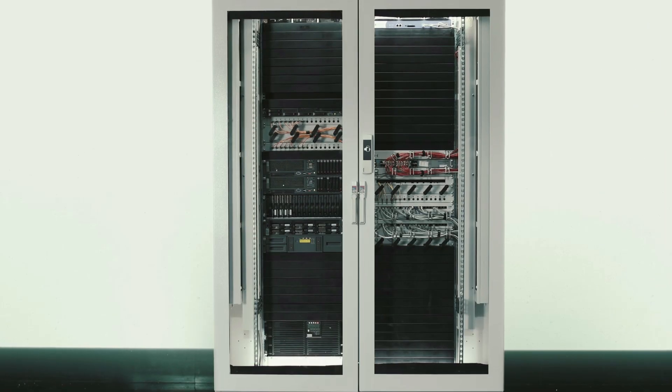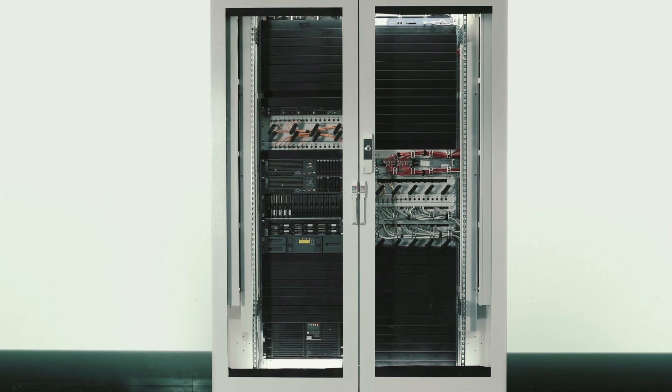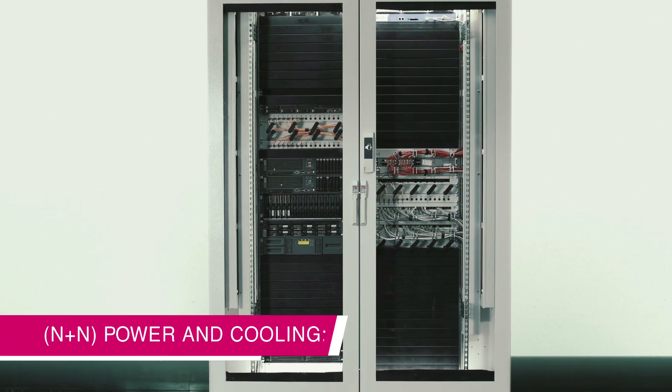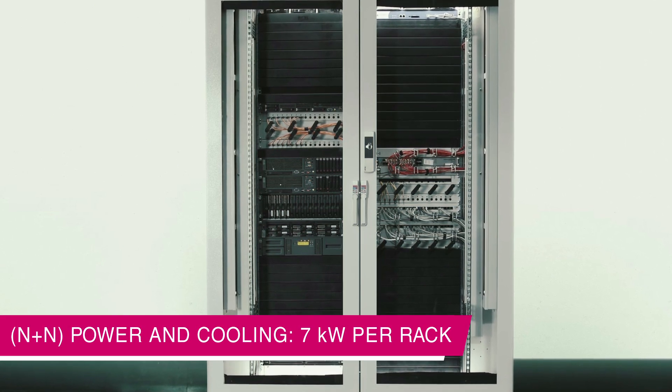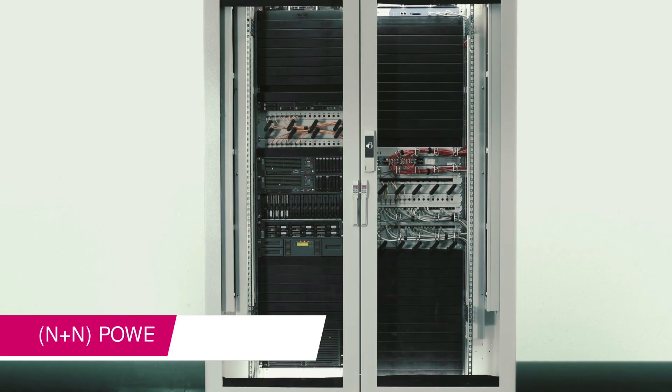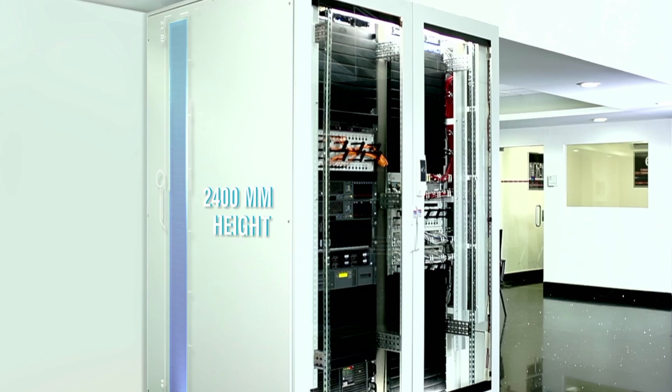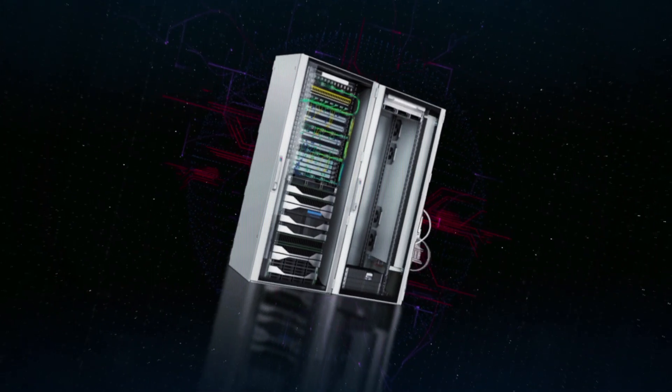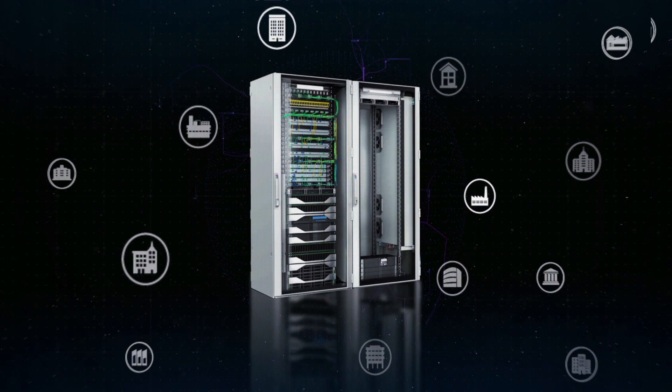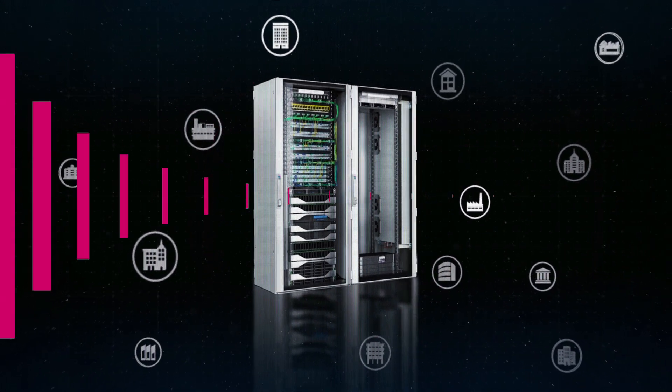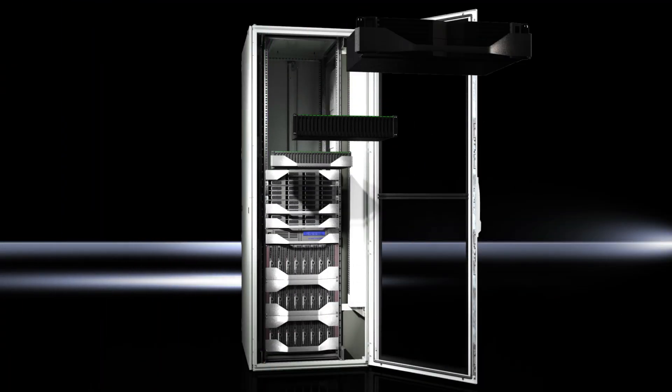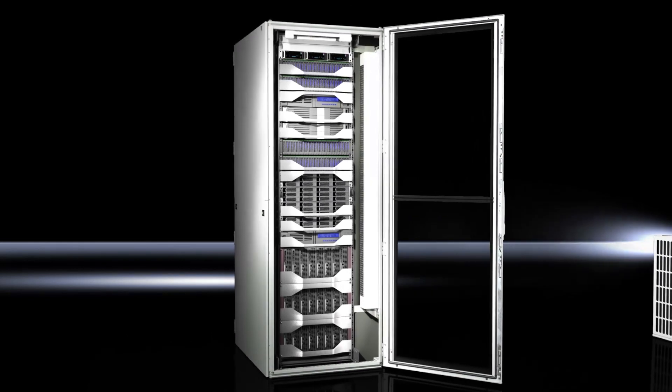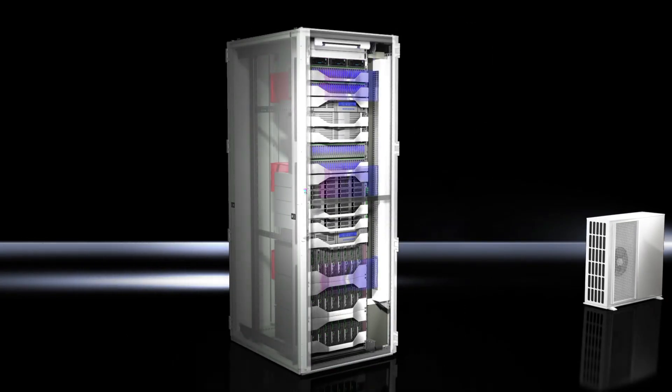Rittal Edge data center is ergonomically designed, with high availability of N plus N for power and cooling of 7 kilowatts per rack. It is a smartly-sized data center that fits into a convenient 2,400 mm floor height without the need of a data center room. It perfectly fits in any office location and supports open IT architecture. It is quick and flexible to install, hence, rapidly deployable in 3 to 4 weeks.